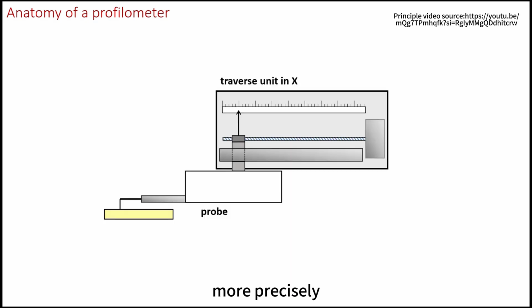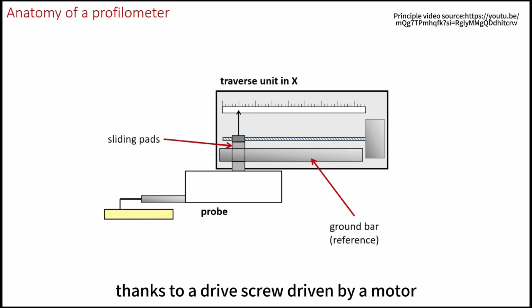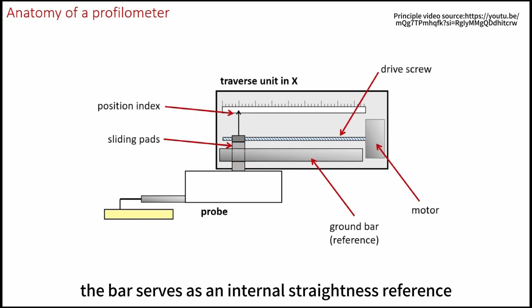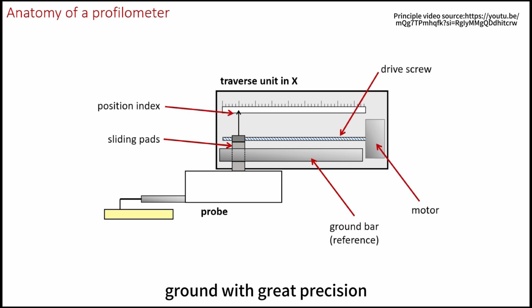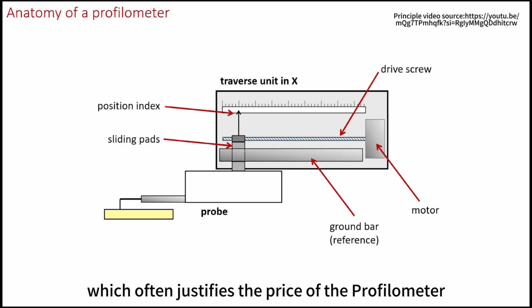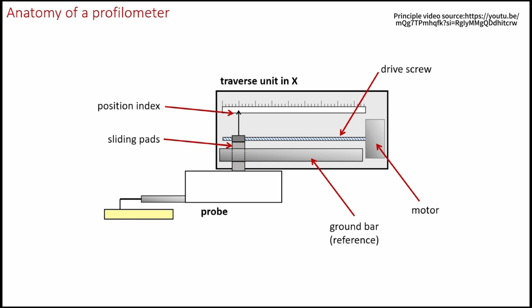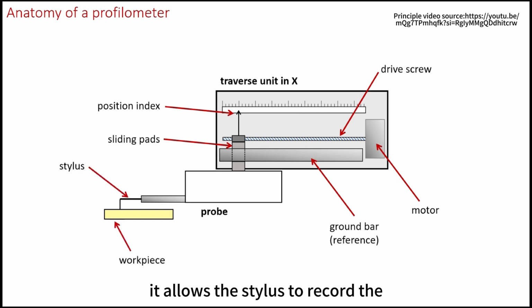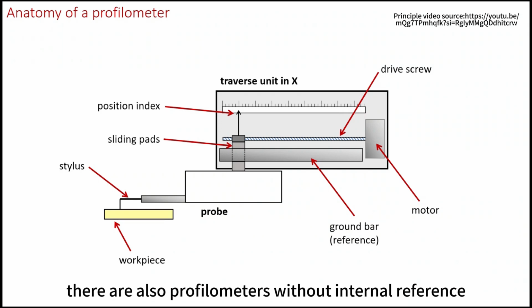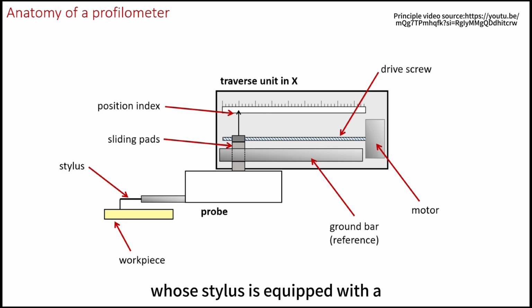More precisely, the sensor slides on a reference bar, thanks to a drive screw, driven by a motor. The bar serves as an internal straightness reference. It is an expensive element, ground with great precision, which often justifies the price of the profilometer. It allows the stylus to record the entire surface texture, be it roughness, waviness, form deviations, or even the form itself. There are also profilometers without internal reference, whose stylus is equipped with a skid resting on the surface, as we will see later.